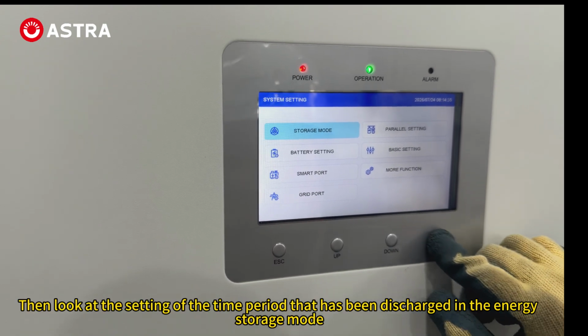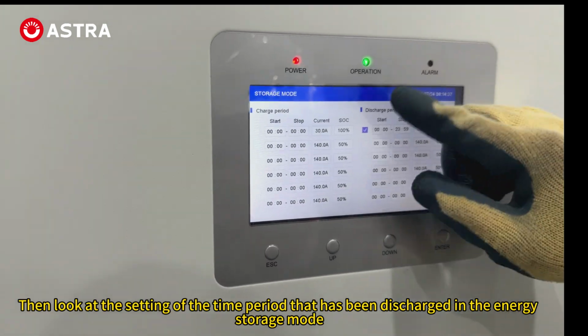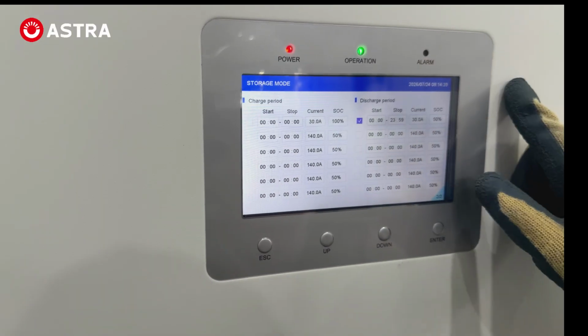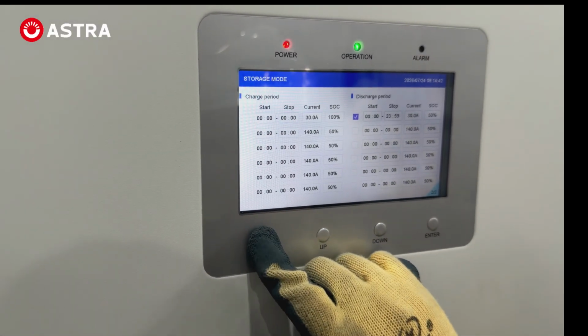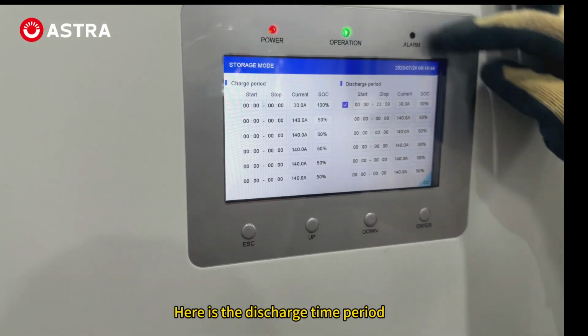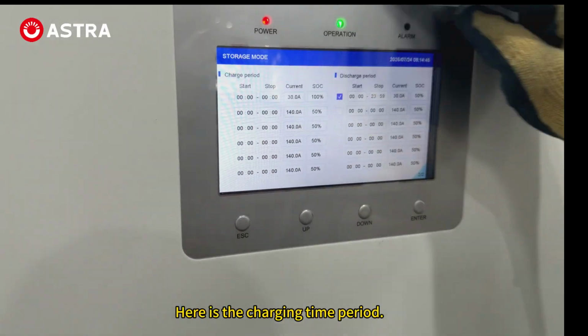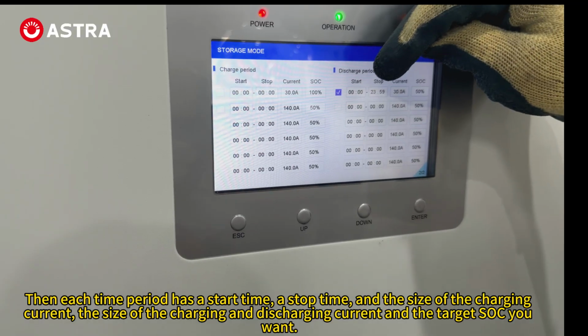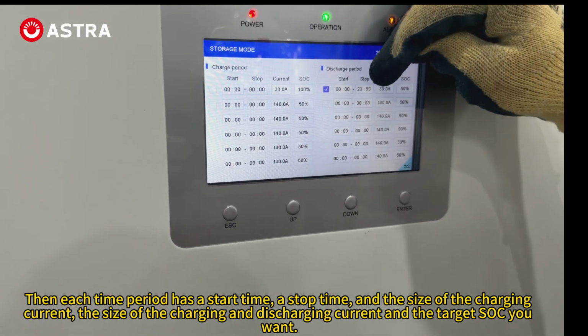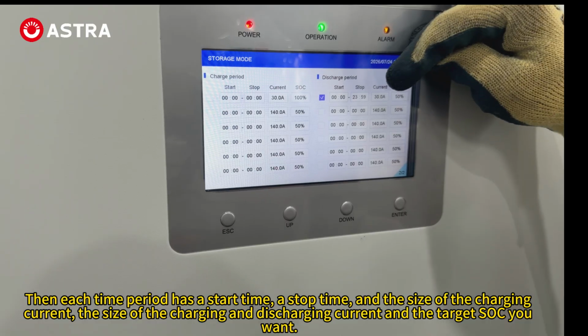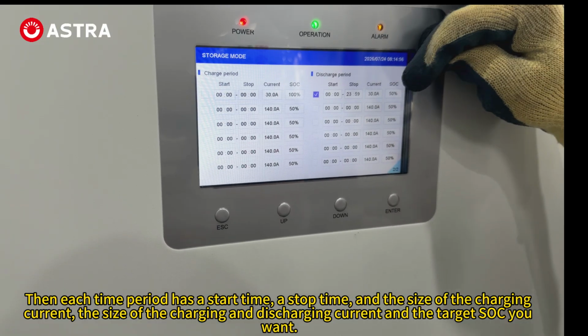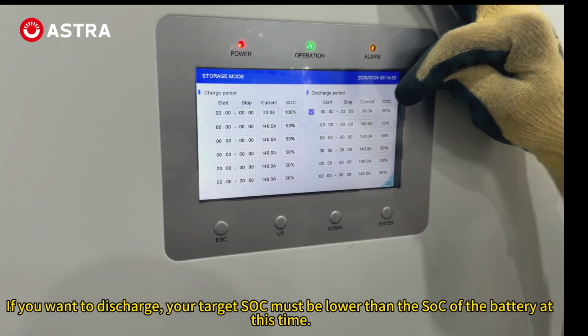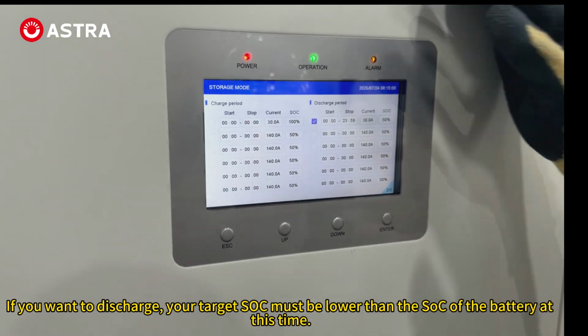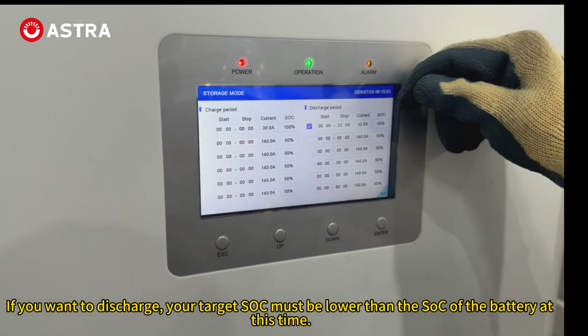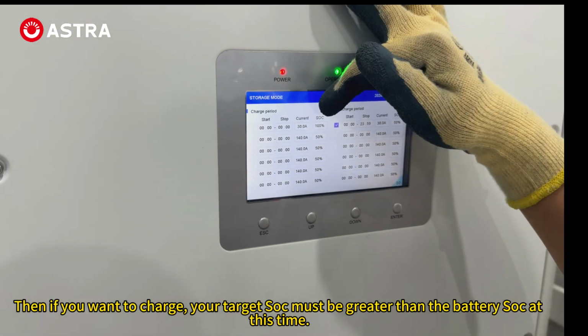Then look at the setting of the time period that has been discharged in the energy storage mode. Here is the discharge time period. Here is the charging time period. Then each time period has a start time, a stop time, the size of the charging and discharging current, and the target SOC you want. If you want to discharge, your target SOC must be lower than the SOC of the battery at this time. Then if you want to charge, your target SOC must be greater than the battery SOC at this time.